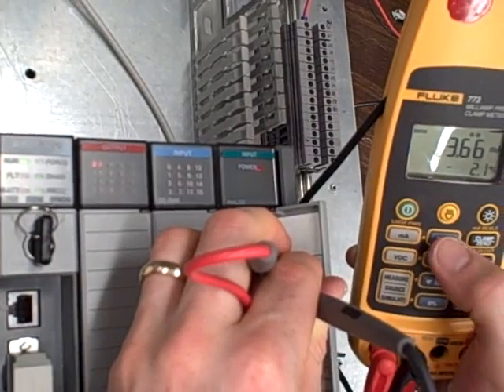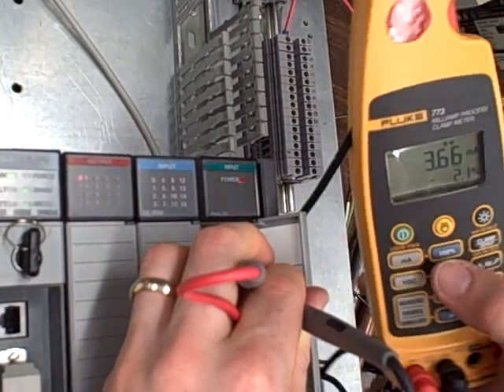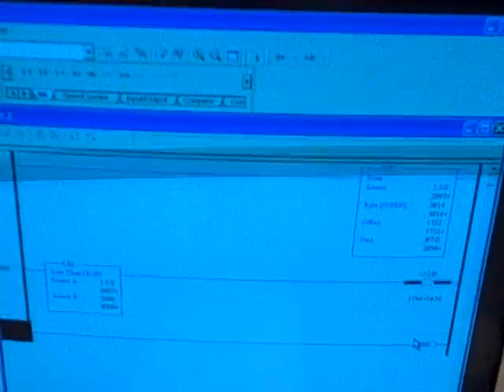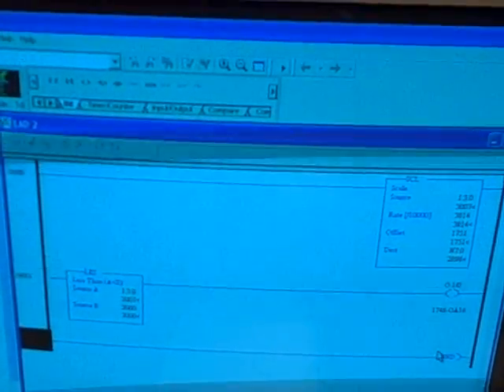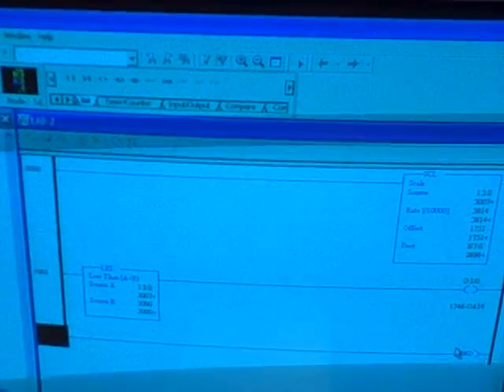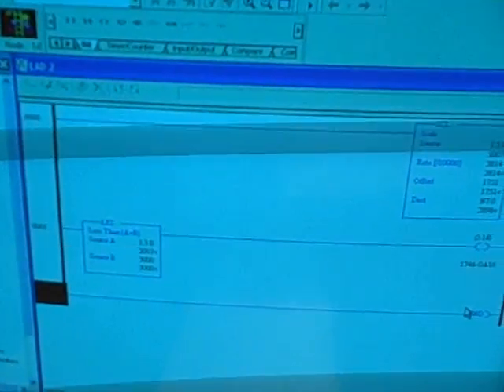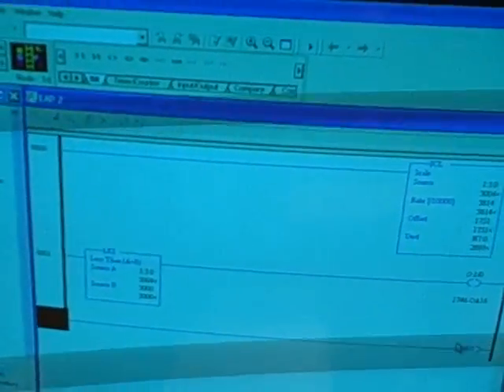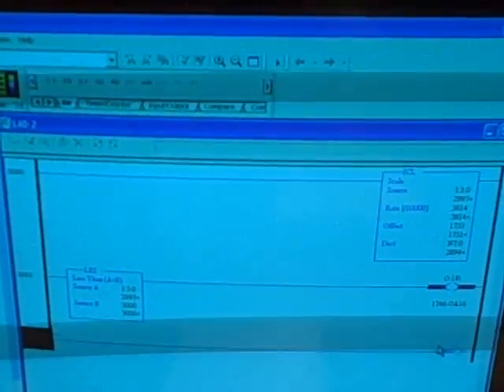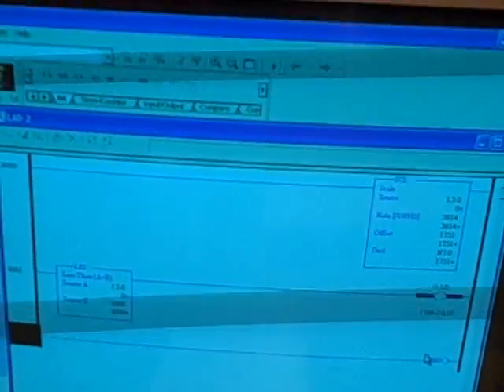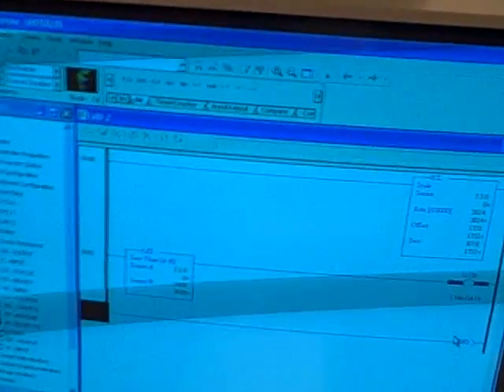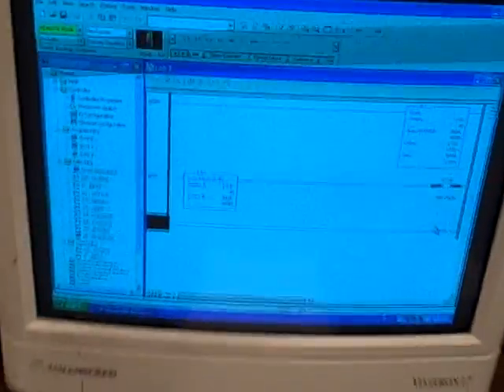So anything below 3.67 milliamps turns that output light on. And that's the count value you can see on the screen of the PLC now. 3.66 milliamps is a count value of 2,997. 3.67 milliamps is a count value of 3,007. Our limit there was 3,000. So we're going right above and right below that limit we programmed in. So we're actually checking the milliamps signal to see if it's significantly below 4 milliamps. And if it is, it turns on the light saying, hey, you have a problem.